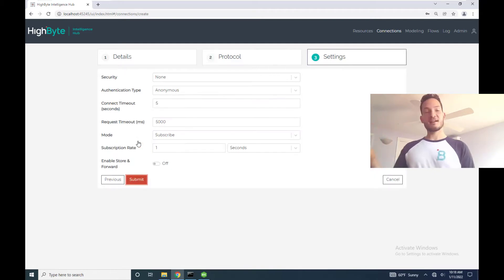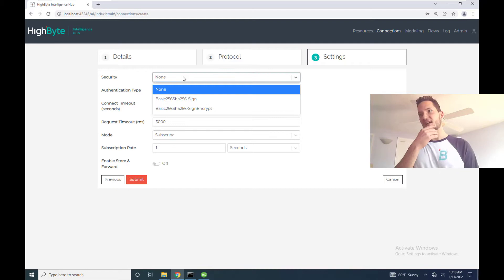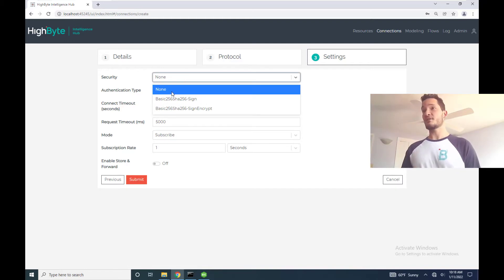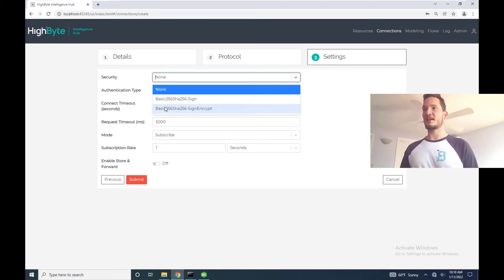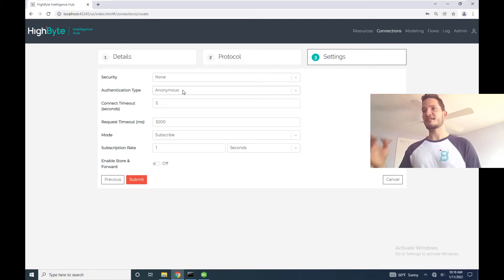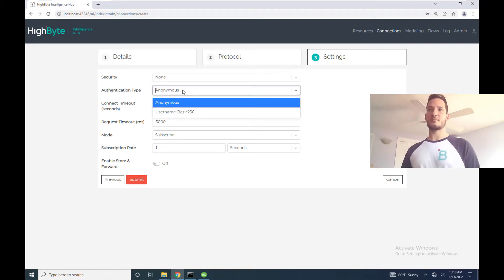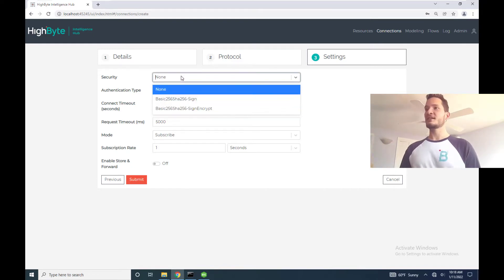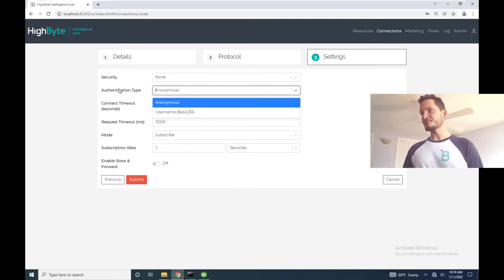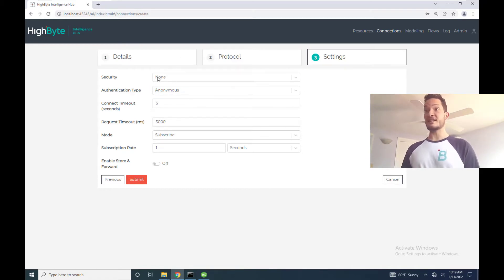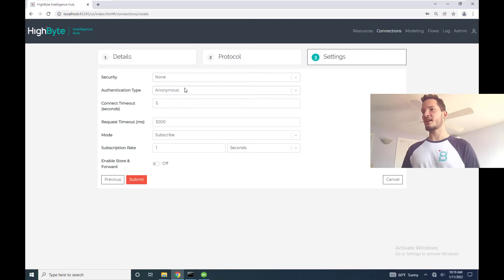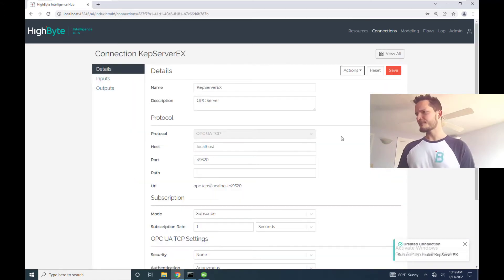Now we get into the security settings. So now I have the option from this drop down to select any one of the options. So either no security, basic 256 sign, and basic 256 sign and encrypt. The other security setting that I have is this authentication type which is set to either anonymous or username. Here we have our two levels right? A security policy and whether or not to use passwords. So just to start out I'm going to leave this as insecure as possible. I'm going to select none and anonymous and then leave all the other settings as defaults.